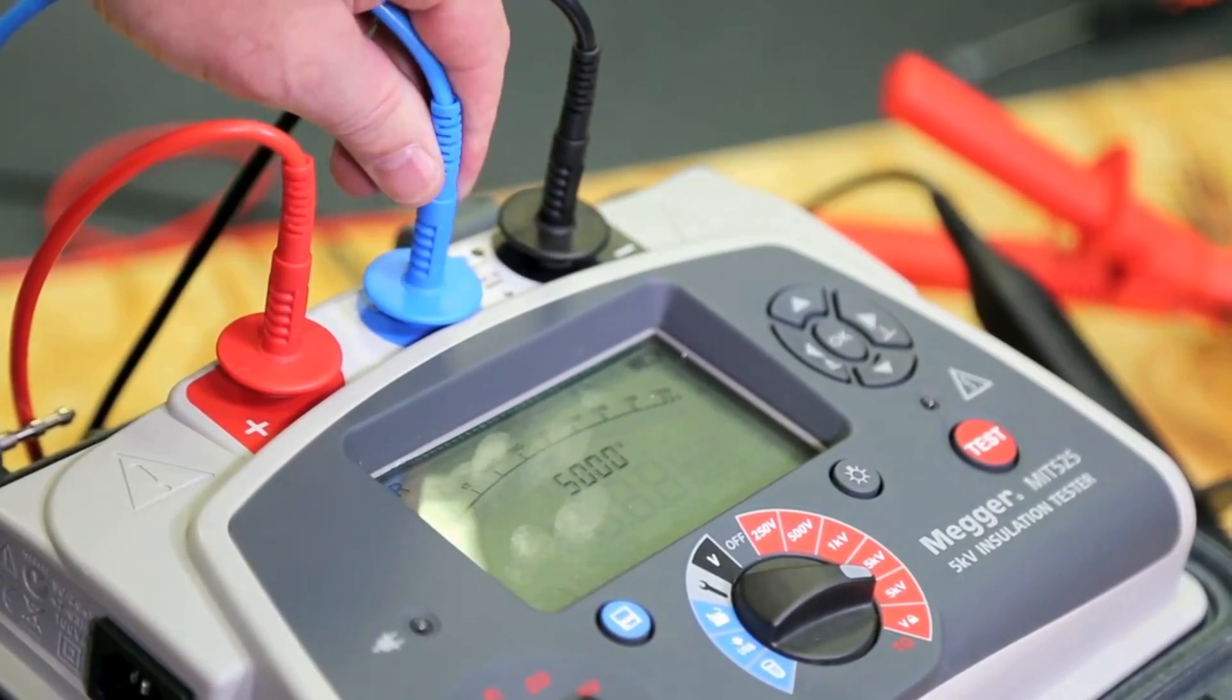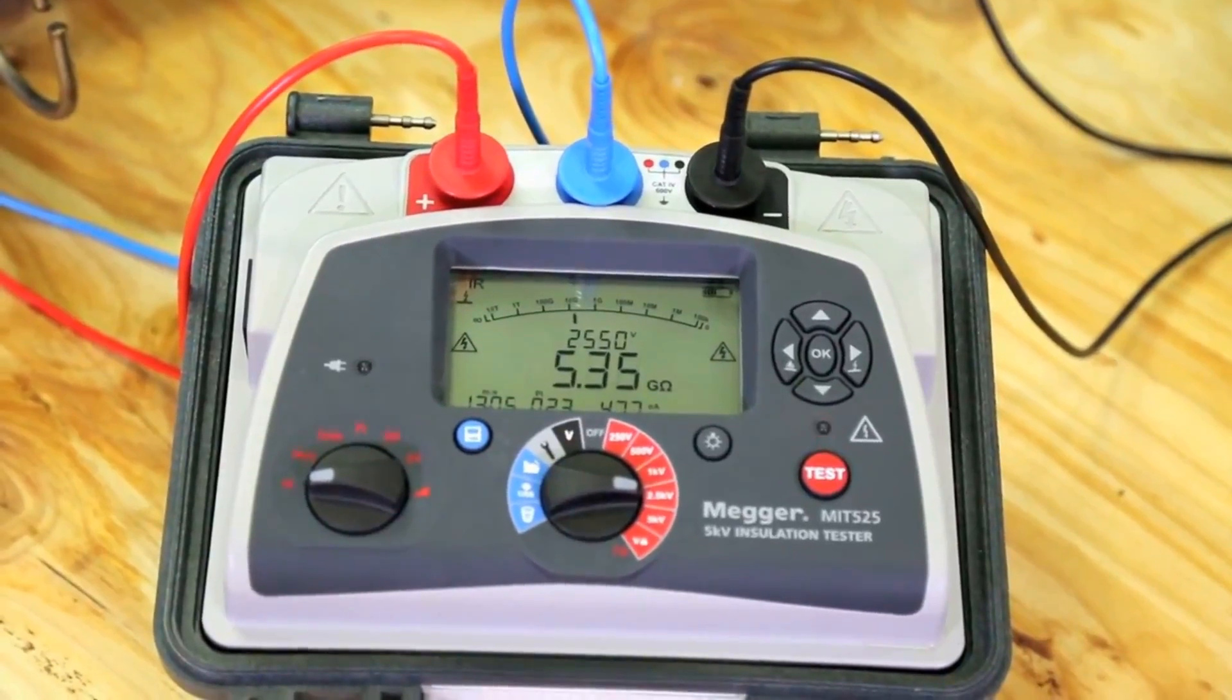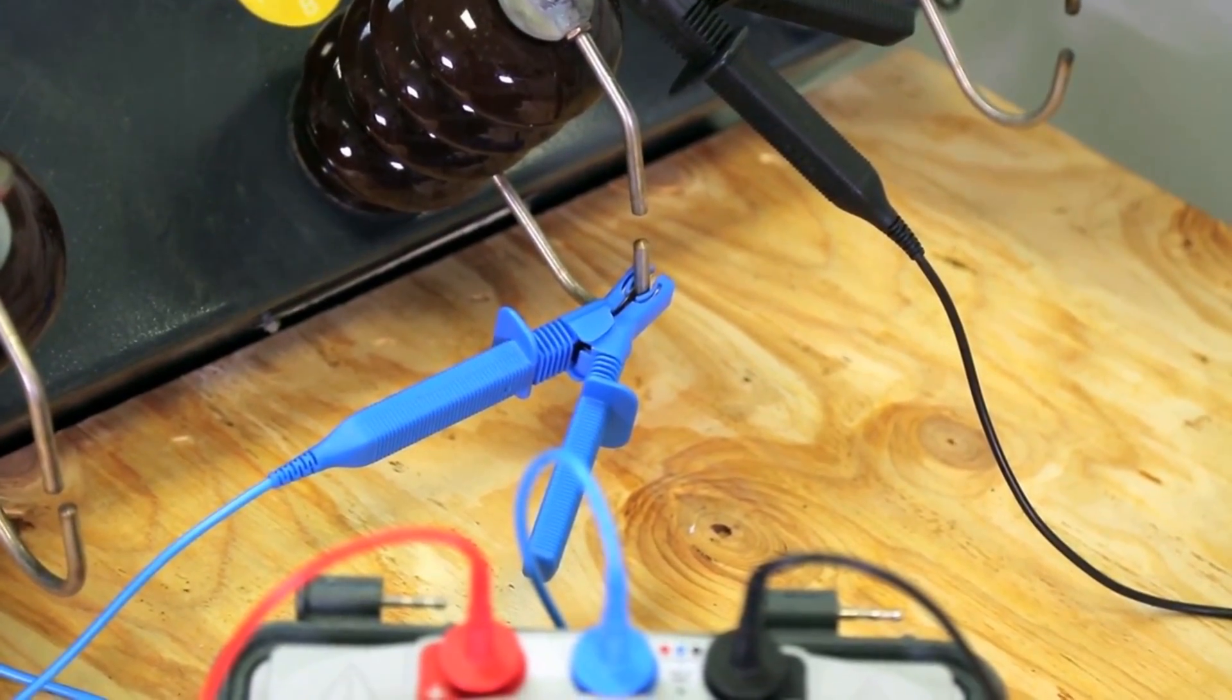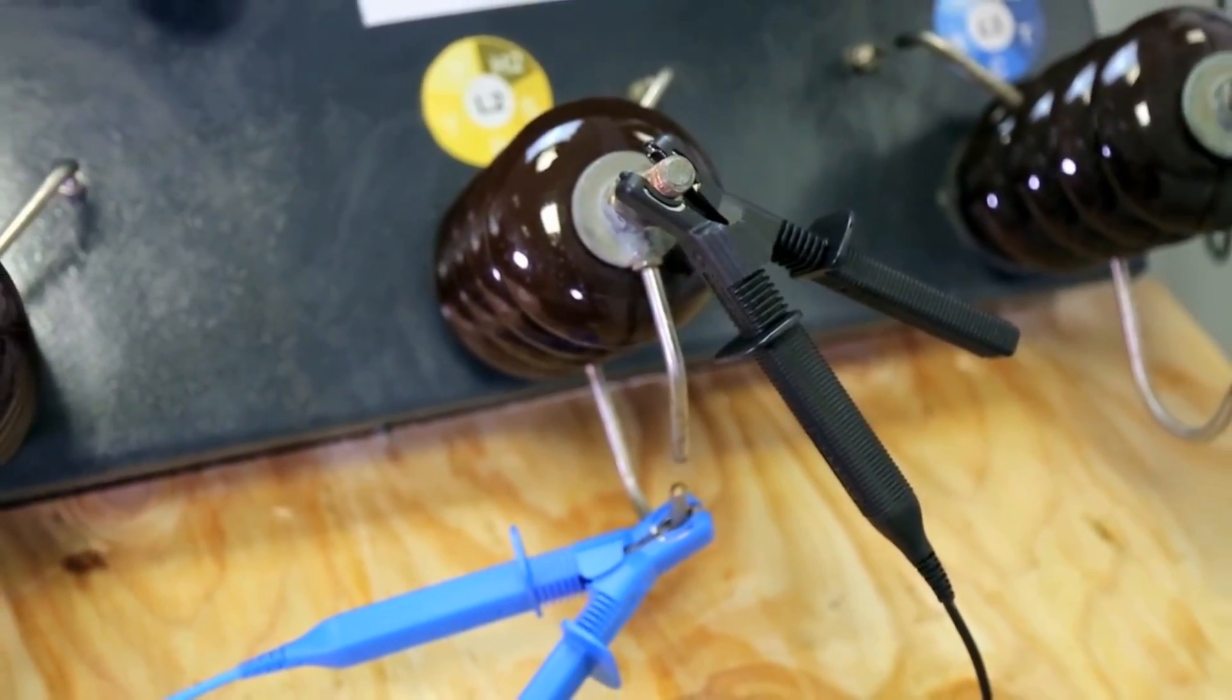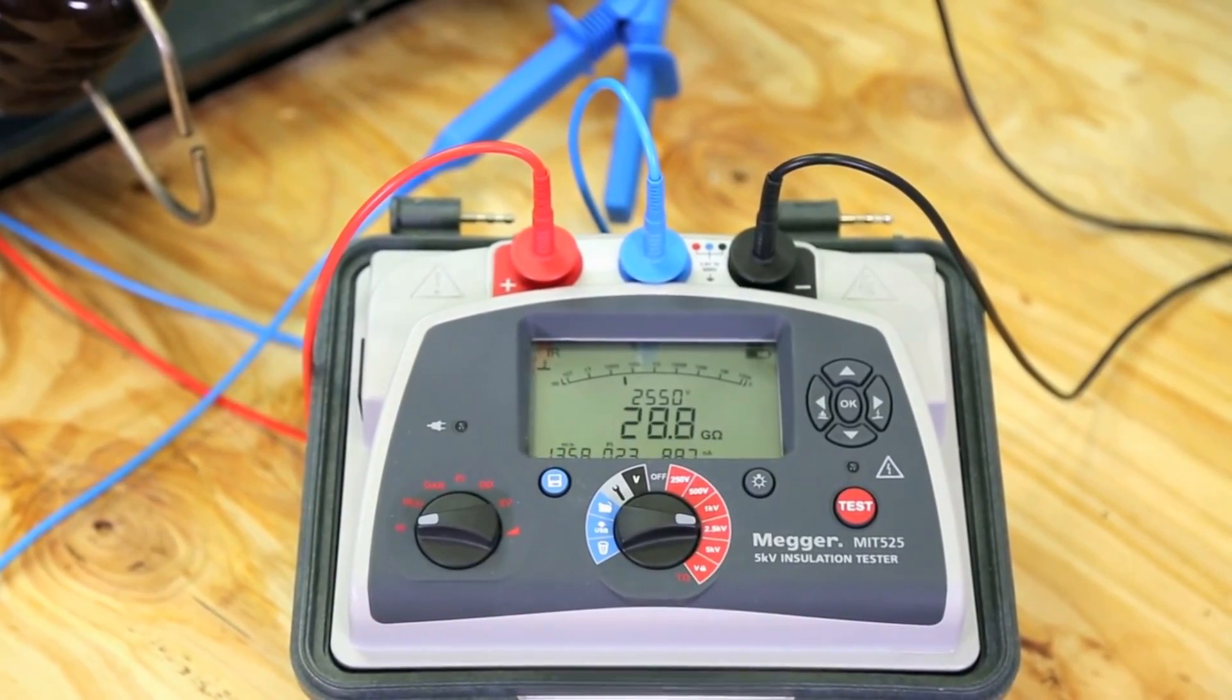The guard terminal ensures you measure the insulation that you want to measure. It measures and discounts any surface leakage current. It is key to the accuracy of the insulation tests. That's why Megger's guard terminal performance is specified and offers unmatched accuracy.